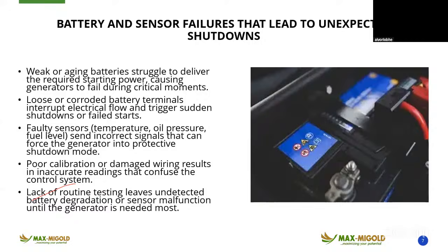Oil sensor too. If there's a loose connection in the oil sensor, you have to ensure that it is properly tightened, firm to where it is meant to be connected. If there's a loose one, it will be shutting down the generator. Because there's a partial contact, it is contacting and losing contact, so there will be intermittent shutdown. What you need to do is ensure that all these sensors are properly tightened and firm to where they are meant to be. Poor calibration or damaged wiring results in inaccurate readings that confuse the control system.